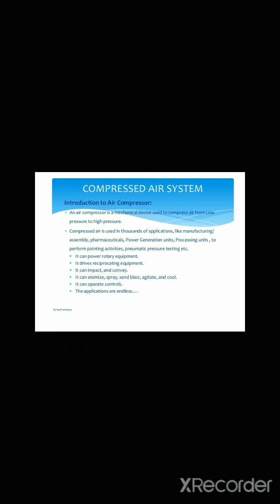Whenever we think about air compressors, there are a number of applications and classification types and subtypes available. Compressor types have basically two main types: the first is positive displacement and the second is dynamic. Positive displacement has two types, reciprocating and rotary. Reciprocating again has three types: single acting, double acting, and diaphragm. Rotary compressors have five types: lobe, liquid ring, screw, scroll, and vane type. The dynamic type has subtypes centrifugal and axial. So these are the overall classifications of air compressor systems.